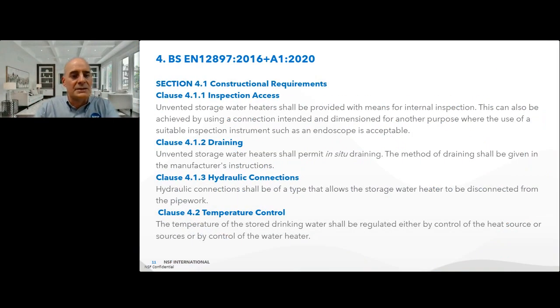Section 4.1 of the standard then covers the constructional requirements. So clause 4.1.1 is inspection access. Unvented storage water heaters should be provided with means of internal inspection. This can also be achieved by using a connection intended and dimensioned for other purposes, where the use of a suitable inspection instrument such as an endoscope is acceptable.